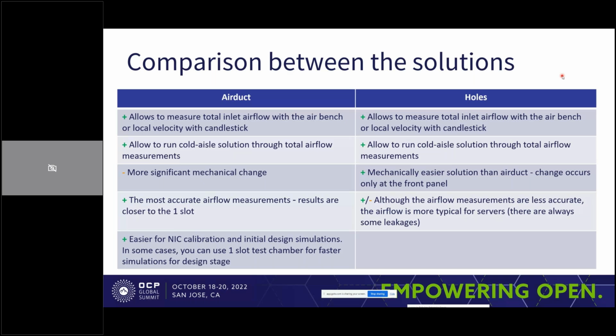The air duct is the most accurate, gives us the most accurate airflow measurements. So the results are very close to our one slot. But for holes, the measurements may be less accurate because we see these different trends—sometimes it's a little bit hotter than one slot, sometimes a little bit colder.